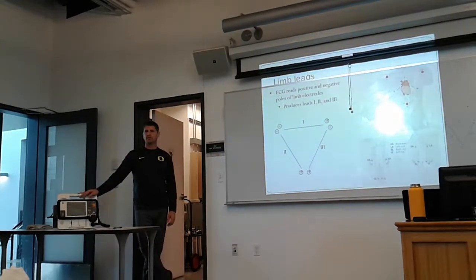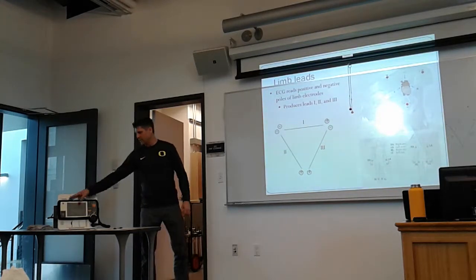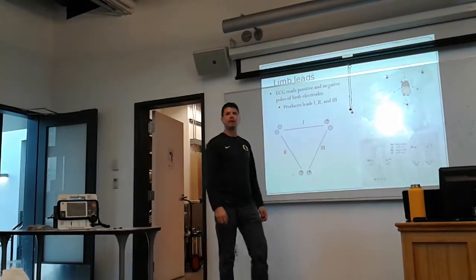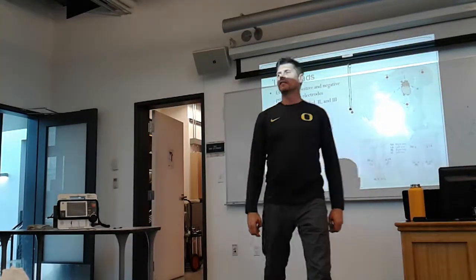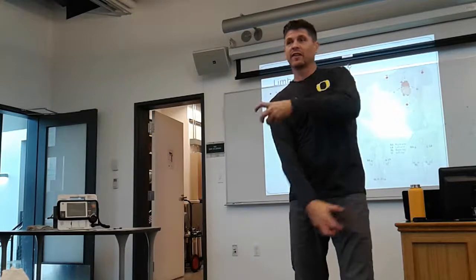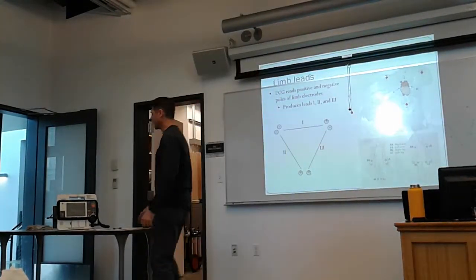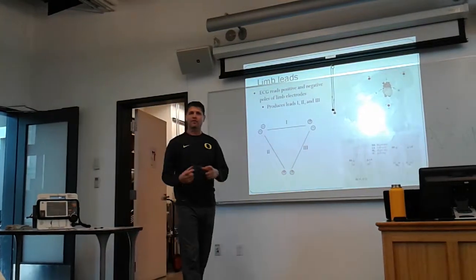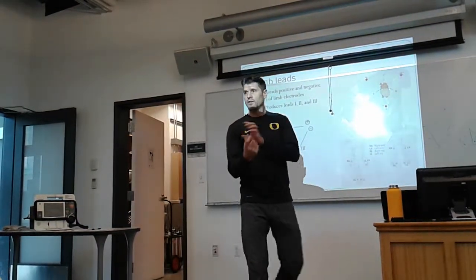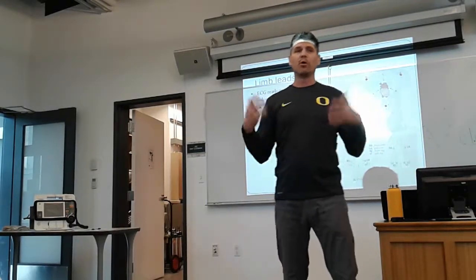It's a 3-lead unit. The only difference is that the machine, Medtronic, was able to come up with a way that instead of having to remove the wires and physically rotate them around the body, the machine itself figured out how to make the wire that is traveling to that particular leg have multiple uses.